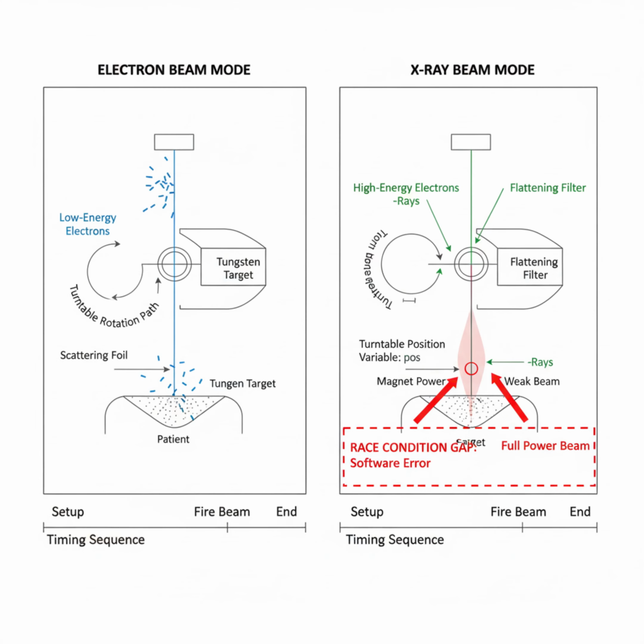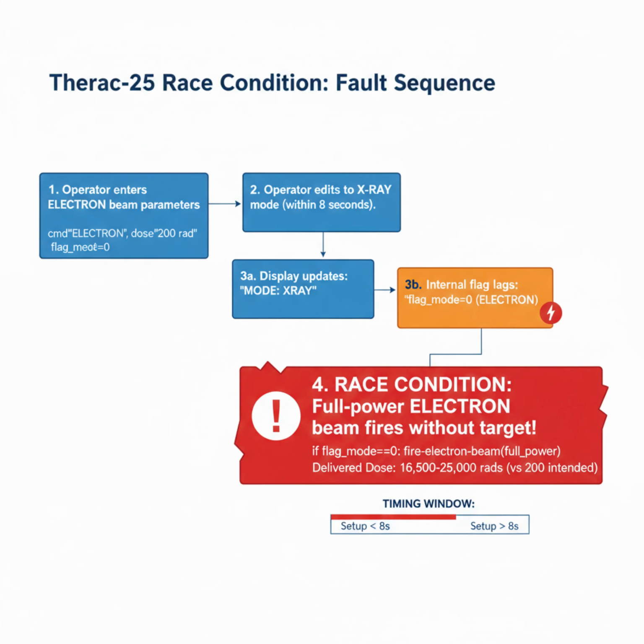Between these modes, a turntable mechanism had to rotate. In X-ray mode, the tungsten target and flattening filter had to be in the beam path. In electron mode, these components had to be out of the way. The Therac-25's predecessors, the Therac-6 and Therac-20, used mechanical interlocks. Physical switches confirmed that the turntable was in the correct position before the beam could fire. If the target wasn't in place, the machine couldn't activate.